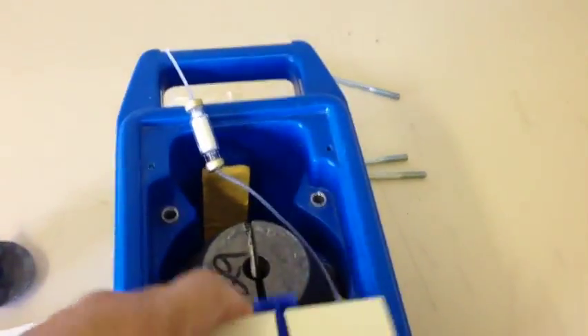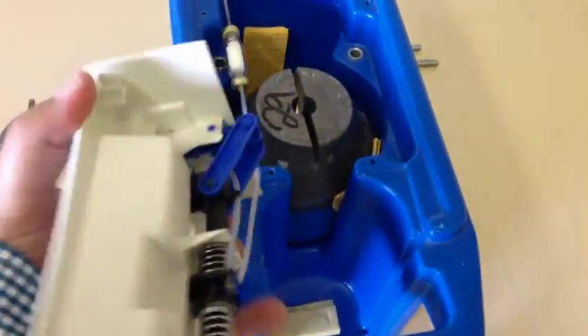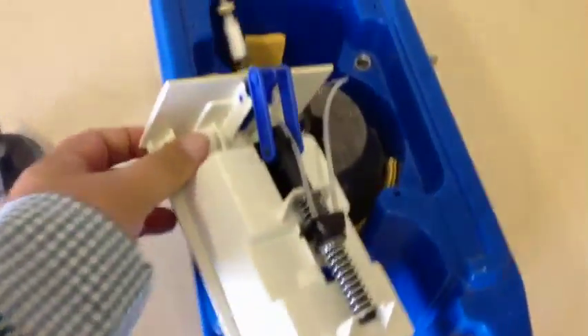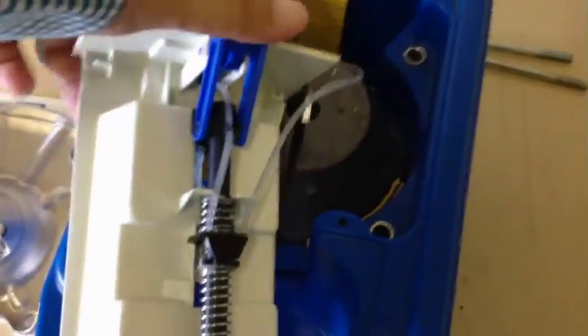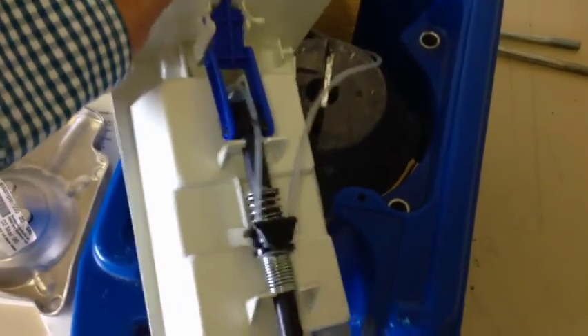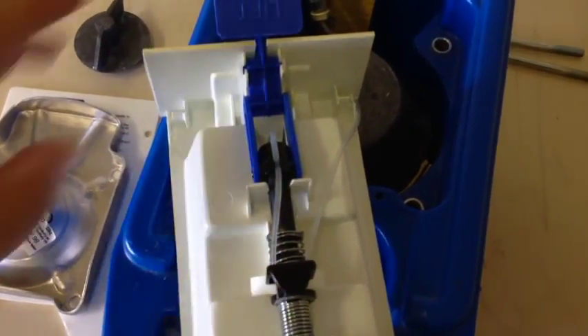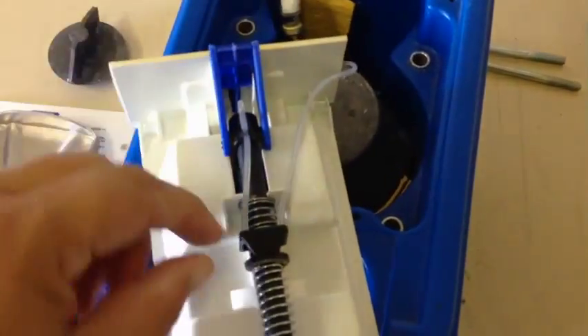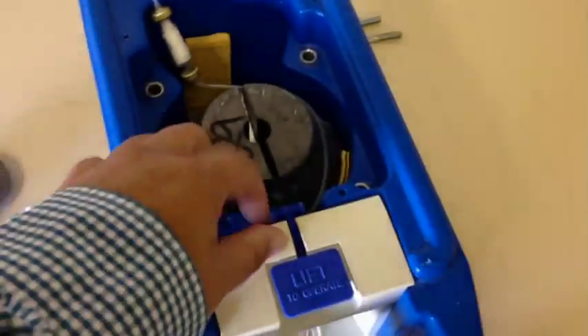The mechanism itself just lifts out. It's very modular and lifts out. On the back you can see you've got a spring-loaded mechanism. As that lift lever is lifted, it releases the spring and allows the flow of saline through the network. When it's down, it blocks that off, clamps it off, and you don't get that flow. So that's the wet generator we used to use a few years ago.